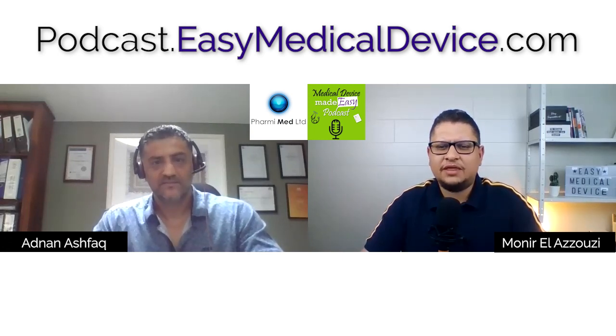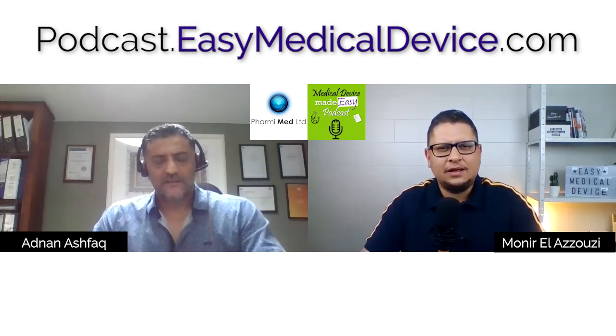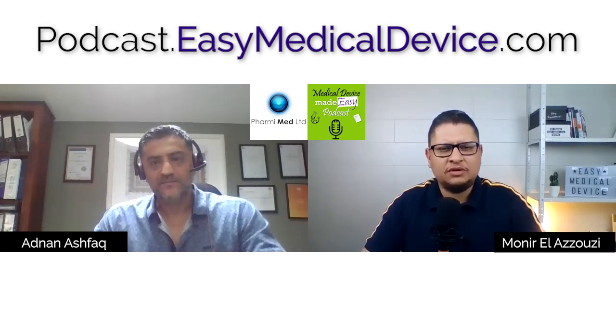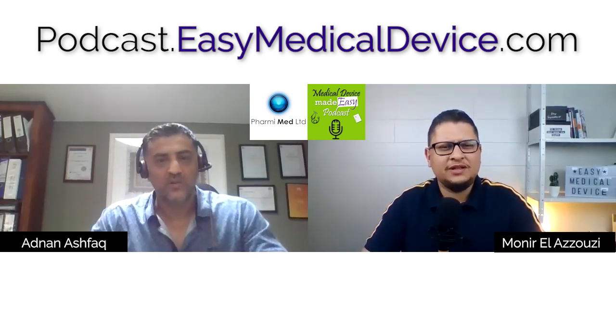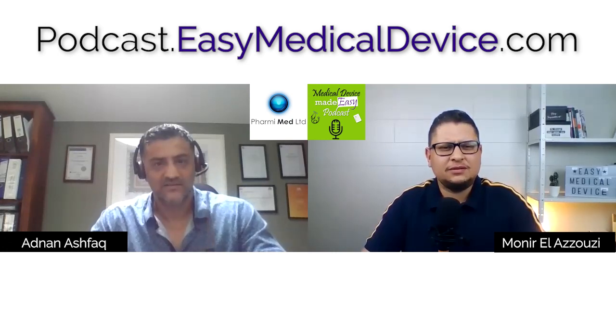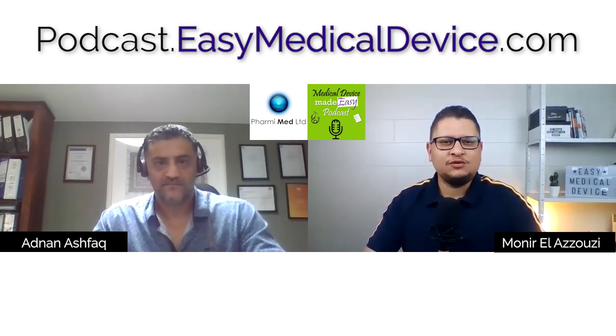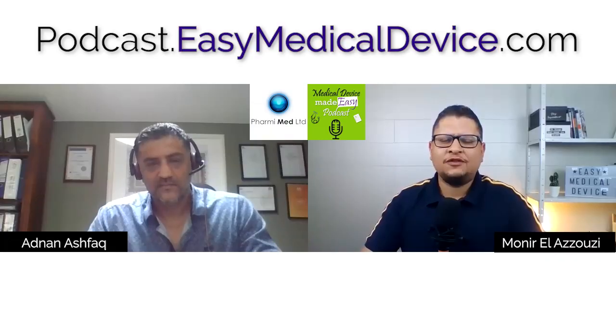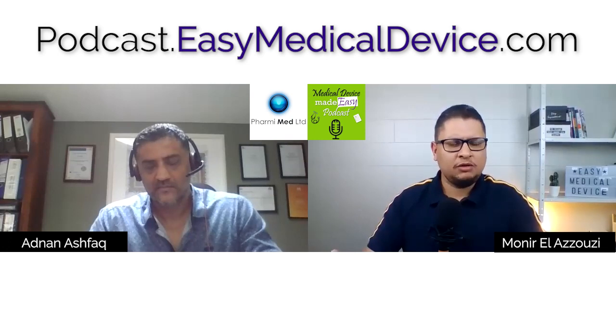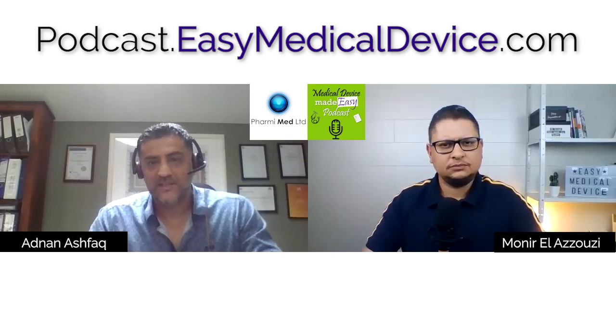No, it's great. I think there is also this guidance from MDCG, I can't remember the number, that is also 2019. It's 2019-11. Okay, so this one is really helping also to define, to qualify if a certain software is a medical device, and also to help in terms of classification. So I think, as you've said, we have first to go to this route before really arriving at the next level, which is maybe this standard, and if we have to apply it. 62304 is only for medical devices, or it can be for any other software? It's specifically for medical devices.